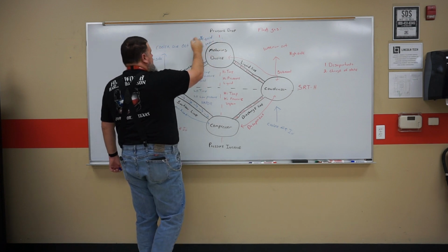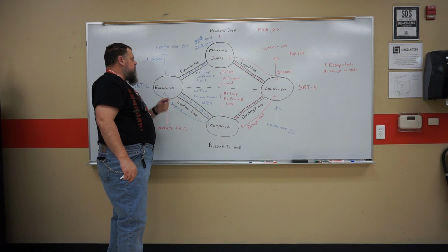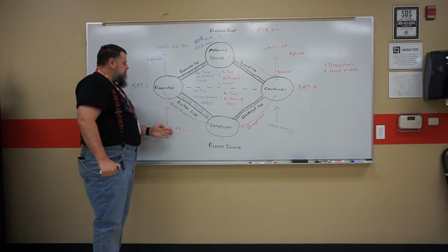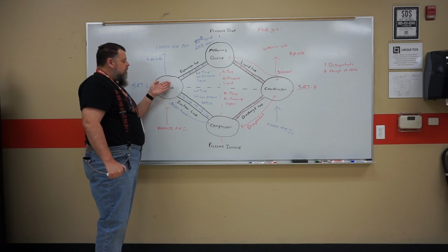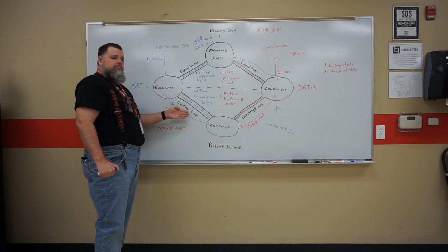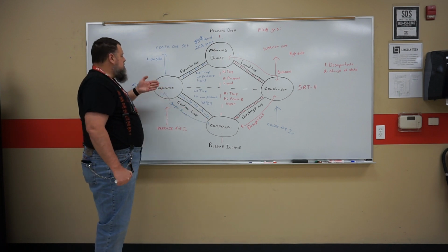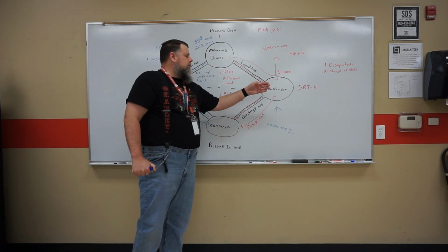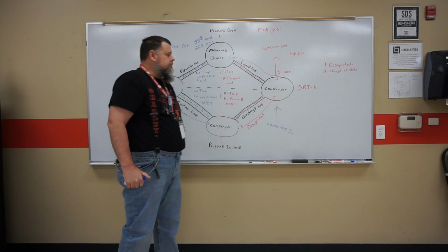That means we've got at least 80% liquid going into our evaporator, and that is where another change of state takes place. That's where the heat that's being blown across this evaporator is going to cause that to boil and turn into superheated gas as it goes back down to the compressor. So basically we're absorbing as much heat as we can. We're going to reject as much heat as we can right over here.